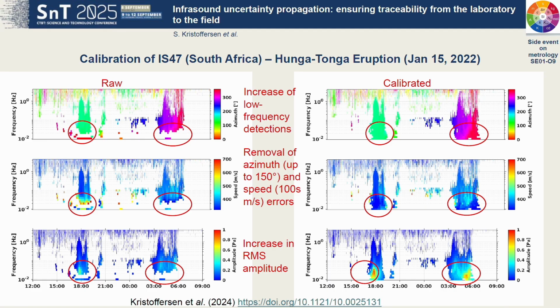And I think what's interesting, or the added value of the calibration, is when this station has a reference calibration co-located with the sensors under test. And so I was able to use those calibrations, apply them to the signals, to deconvolve the signals with those calibration responses, and then we get the figure on the right. And we can see now we're filling right in all the way down to 0.01 hertz. Our azimuth and speed, we're no longer seeing those biases show up.